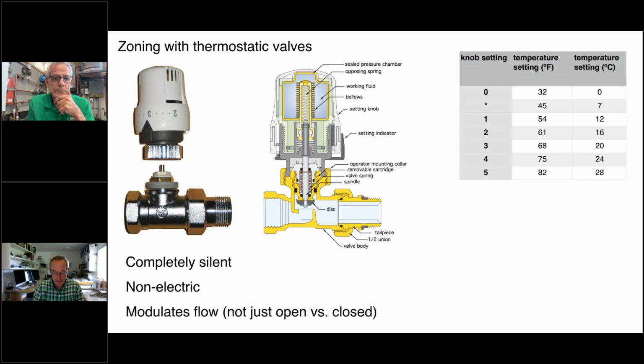I really like non-electric thermostatic valves. They're what I call simple but elegant devices, and very underutilized in the U.S. market. I mean, you go to Europe, you go into a castle that's 200 years old where they retrofitted panel radiators, you see thermostatic valves, and they just use them everywhere. It just makes sense: a non-electric, proportional zoning device. It doesn't get any better than that, because that's the thing in a castle. How do you get wires to all these different rooms? You just put a TRV on there.